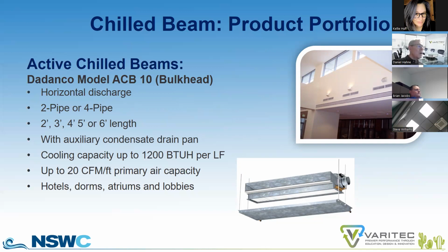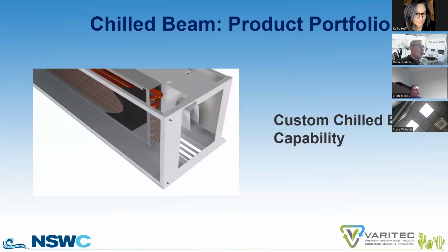You certainly don't want water damage coming down onto your ceiling or down onto the floors of a building. So this is one solution for doing that. Plus, they can also be piped for condensate drains as well, and can work in that solution, in that unique application. Chill beams are very architecturally adaptable. A manufacturer that we work with, Dadanco, is willing to look at custom chill beams and how they might be applied.